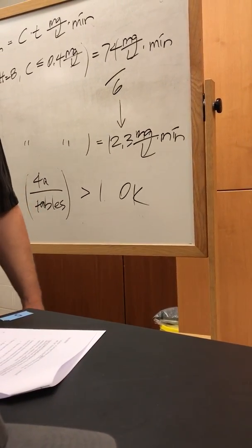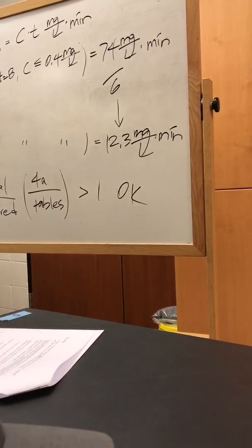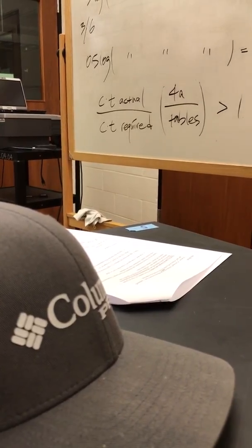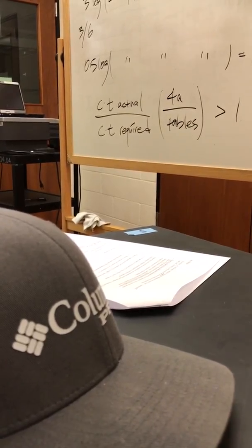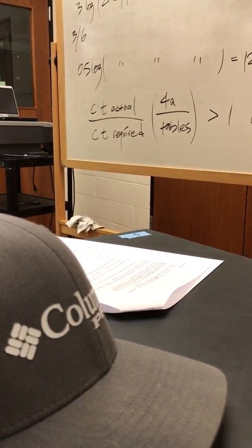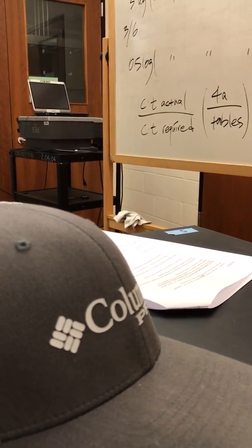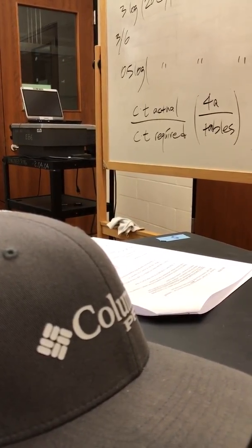And they ask you what's the ratio. And then it says, how does it compare to the requirement? It gives you, in this problem, everything that Dr. Thomas is talking about. It gives you the 0.5 log numbers, so you don't have to do any conversion. Because we have such little chlorine coming out of the faucet, which we're going to use for testing, we're going to use the 0.5 log, which is 68 percent reduction, I believe. Yeah, 68% reduction. So we're going to use that 12.3 milligrams per liter concentration number if you have this.